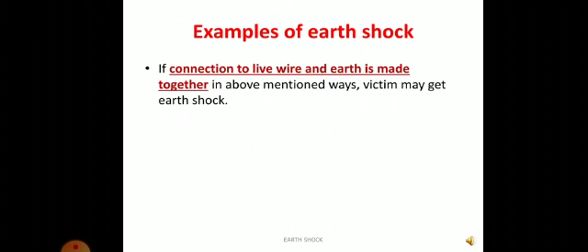The department should be designed with proper earthing facility. Just using 3-pin plugs isn't safe by itself; the building must have good earthing. The socket has 3 holes, and the upper hole should be connected to earth by a conducting wire. Only then can we say we have good earthing facility.